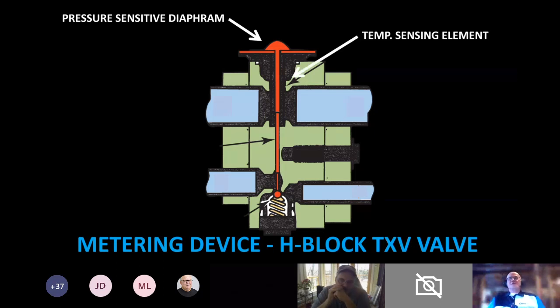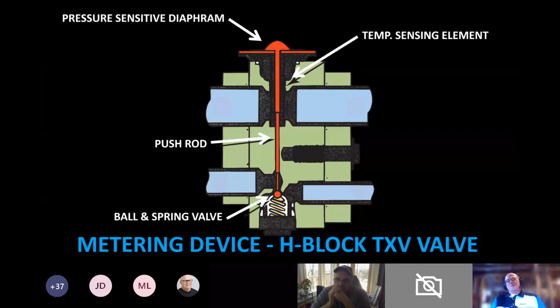There is a temperature sensing element inside, and you can imagine that those two large lines then will be the evaporator, and we can sense the temperature of the refrigerant leaving the evaporator. We have a push rod, and then the actual control of the flow of refrigerant through the H block is a ball valve, and it modulates the flow of refrigerant into the evaporator based on its outlet temperature.